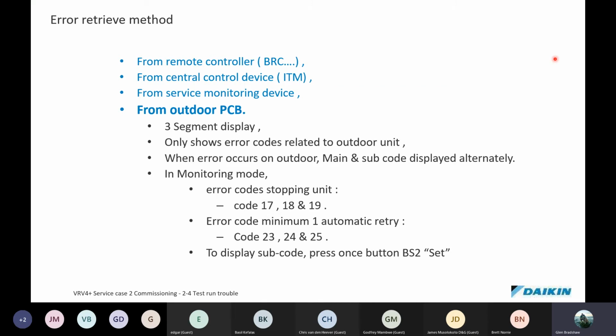So you can actually see whether your system is going through retries, and you can pick those up from codes 23, 24, and 25. These are very important if you get to a site, especially the 17, 18, 19, to use them if you've never been on a site before. They will give you an idea of what's been going on at the site and give you something to start working with. It's kind of like a bit of CSI. You don't have to start from scratch, especially if you also pick up the error codes out of the remote controllers that are inside the memory. Use those as well, especially when you've picked up a site that somebody else has been thrown off of before you carry on. Just have a look at what's been going on.